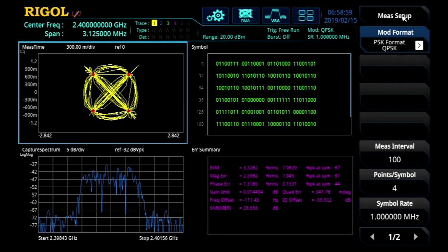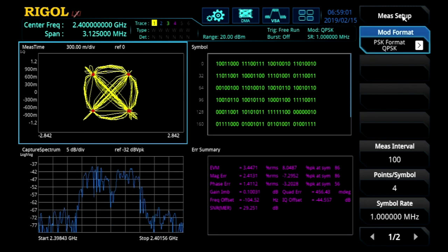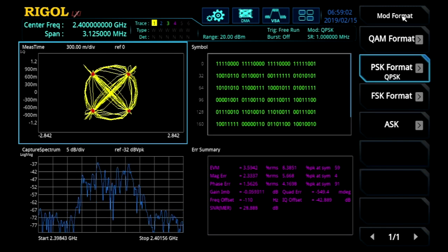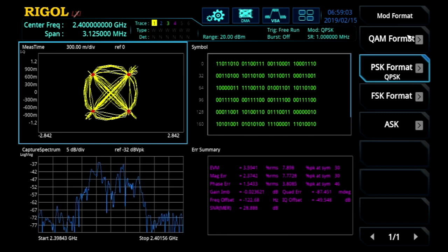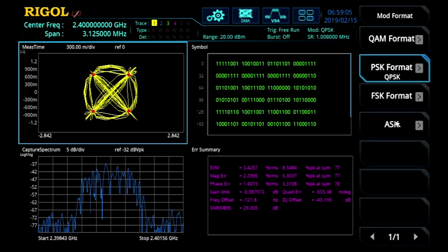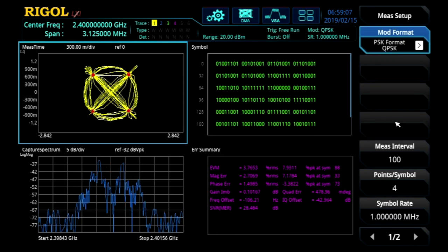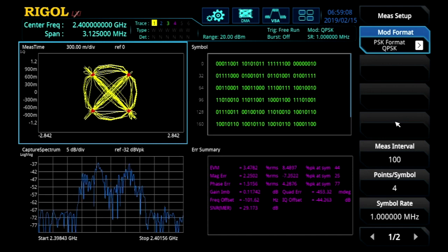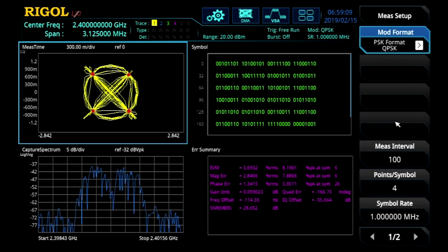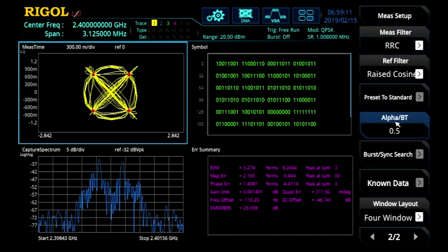Here also in the measure setup, we can select between other modulations, QAM, FSK, ASK. We can set the measurement interval, points per symbol, symbol rate.